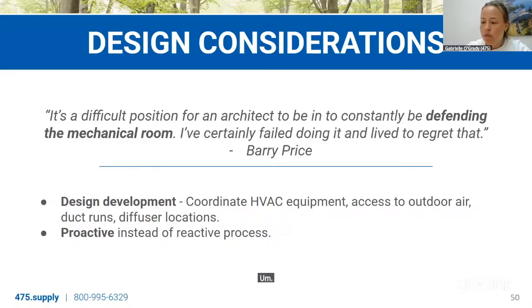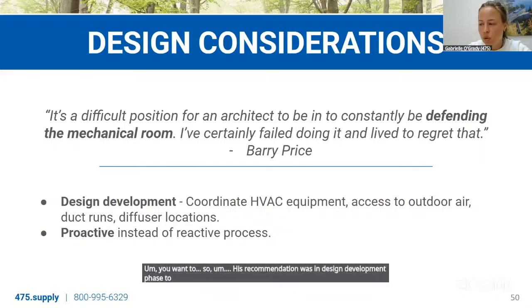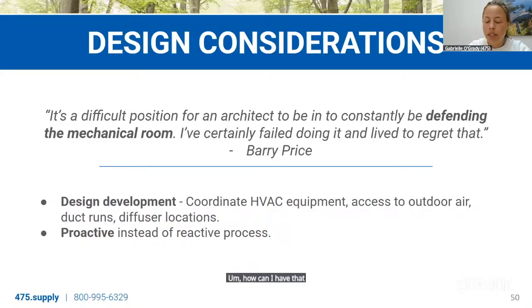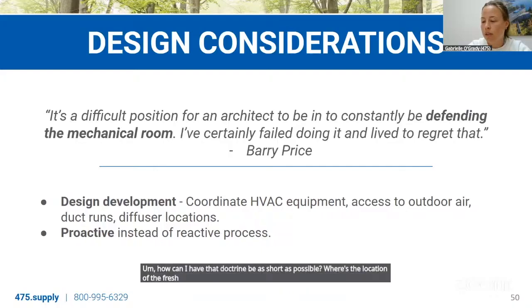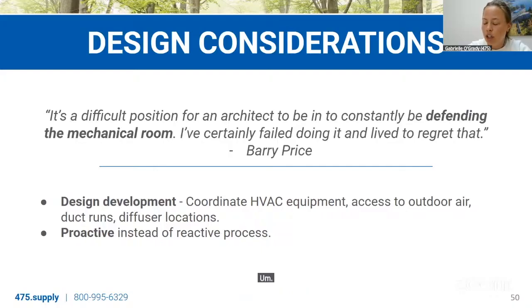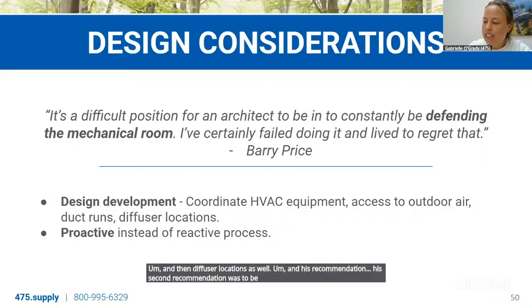So his recommendation was in design development phase to coordinate that HVAC equipment, to start thinking about where's access to the outdoor air. How can I have that duct run be as short as possible? Where's the location of the freshest air possible? And then diffuser locations as well. And his second recommendation was to be proactive instead of reactive.